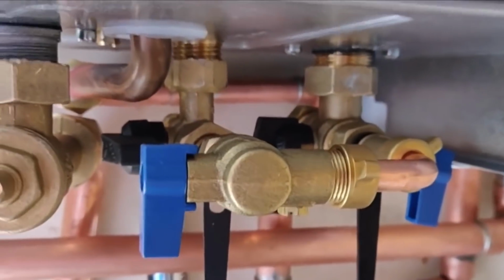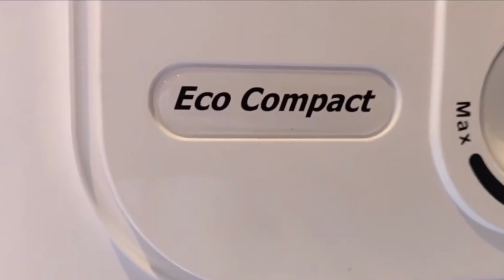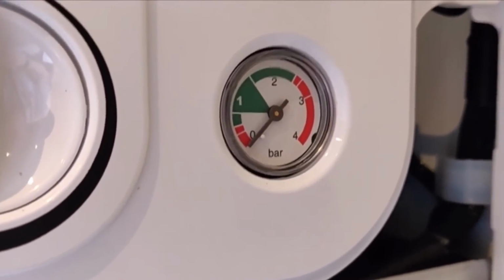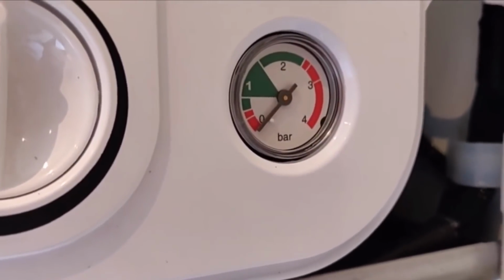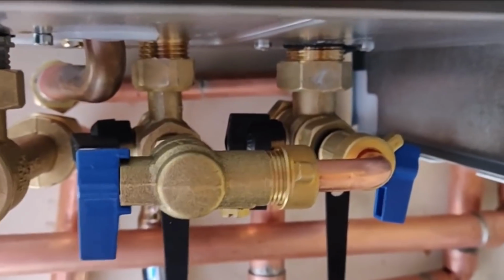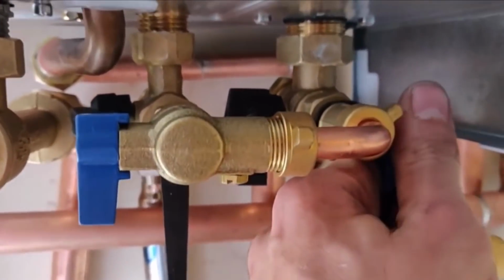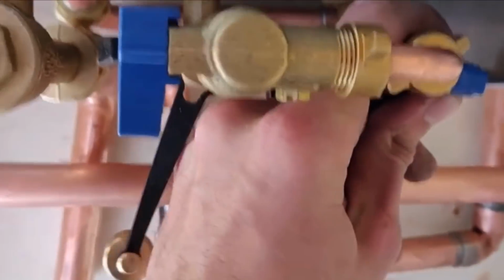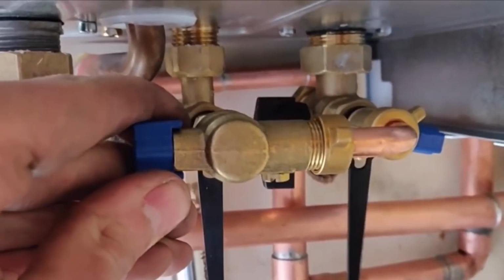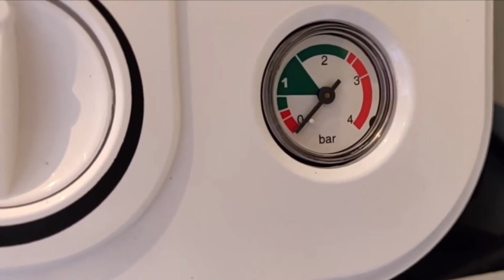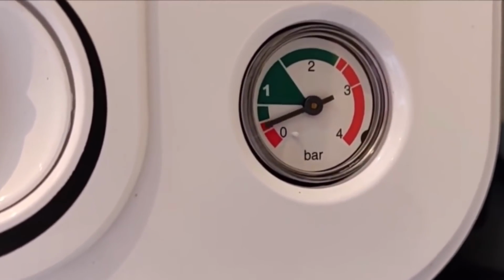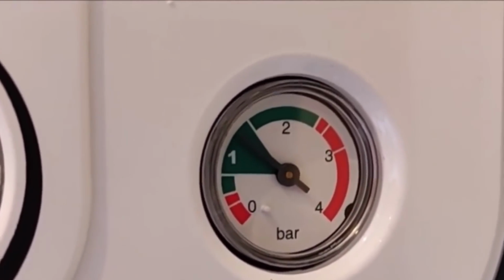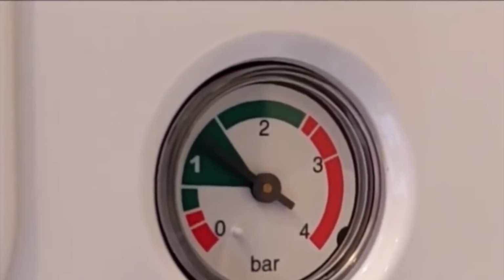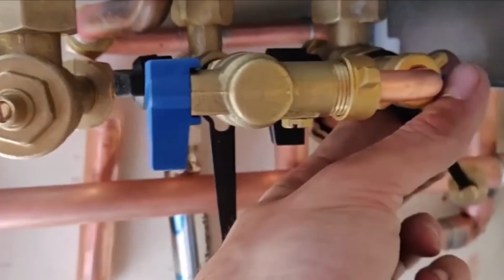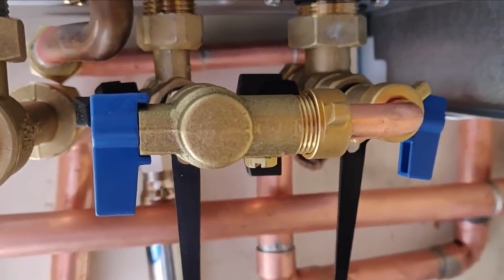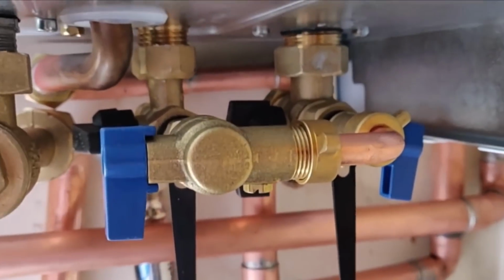This is the filling loop for the main Eco Compact, and it's pretty much the same as the 6 or the 800 to fill it up. You can see the pressure gauge reading 0, and we need to get it above the 1 in the green section, so we go down to the filling loop. This one here on the return, we open this valve fully so it's in line with the pipe. Then this one on the cold water, we just crack it open a little bit. The water will come into the system and we wait for the pressure to rise just above the 1, between 1 and 1.5 in the green section. Once we're happy we're in the right pressure, we can close both valves, and it's as simple as that. That's how you top up all the Baxi boilers.